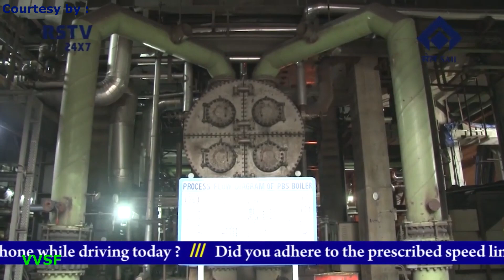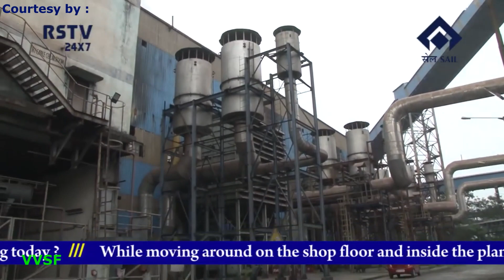The DCS system was technologically upgraded and successfully commissioned in PBS for Boiler 1 and STGs in BPTG. Provision of steam washing for STGs was developed, erected and commissioned. Protection of the house load transformer was implemented through a fiber optic network between CPP1 and PBS, about 4 kilometers apart. A feed control line was erected, tested and commissioned to facilitate smooth hydro testing of all CDCP boilers. The battery charger system in PBS and the AVR system of STG2 were revived in-house, resulting in a cost saving of Rs 12 lakhs.